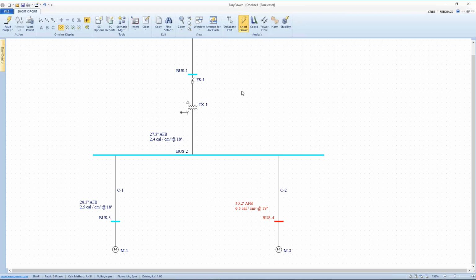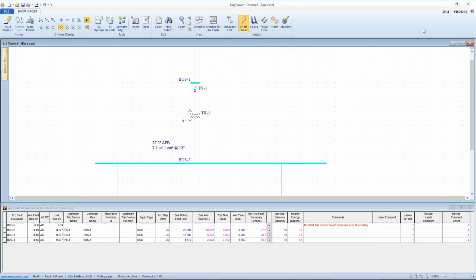Well, the significance, the bottom line, is that the next step in any study that you do when you reach this point is to let the tools show you what's going on and how the calculations are being made. And to do that, I utilize this arc flash icon at the top, which gives me the ability now to look at both the one-line diagram and the calculations that are being made on each bus. If I look at bus 2, it's a 480 volt bus. The protective device is the fuse.